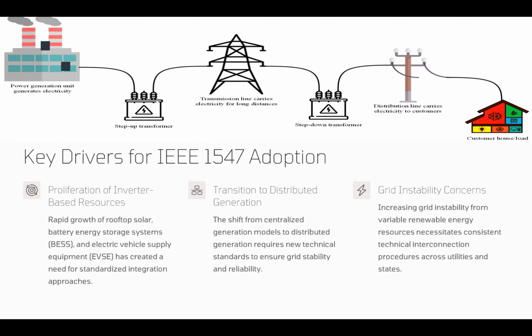Now, why is this important? The traditional grid was developed for large rotary machines with inherent inertia and stable frequency and voltage responses. But inverter-based resources, because they are power electronics and use switching devices, respond much faster. And if they are not coordinated, they can behave unpredictably. They can cause voltage flicker, harmonic distortion, or reverse power flow, which are very important challenges when we talk about the modern power grid. Because of those challenges, we need a standard covering things like ride-through, reactive power support, and harmonic limitation, so we can make sure that those devices coexist safely with our grid.